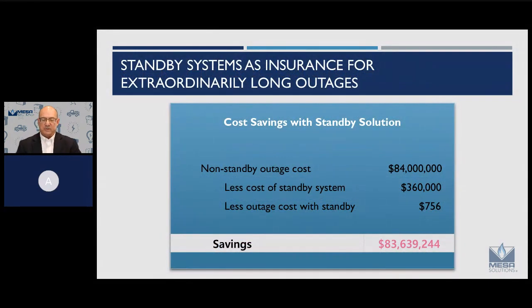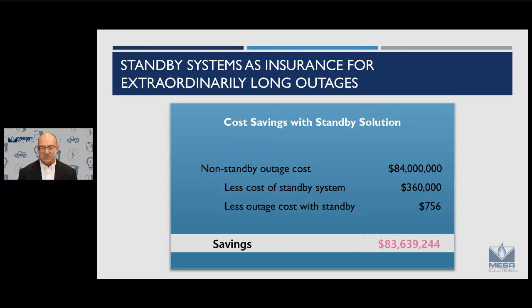Another important case to look at, which may be what most people are ultimately interested in depending on the criticality of your site, is thinking of a standby system as insurance for an extraordinarily long outage. Utility indexes might show the average customer is out for 50 to 200 minutes a year, but every 4 or 5 years, almost any utility system might have a storm or event where some customers are off for 2 or 3 weeks. If you live somewhere subject to ice storms, tornadoes, or earthquakes, there could be significant damage to the utility system, and suddenly you get a really long outage.